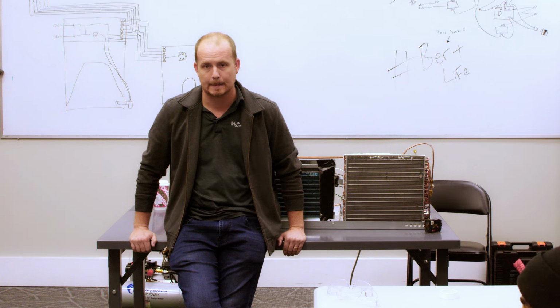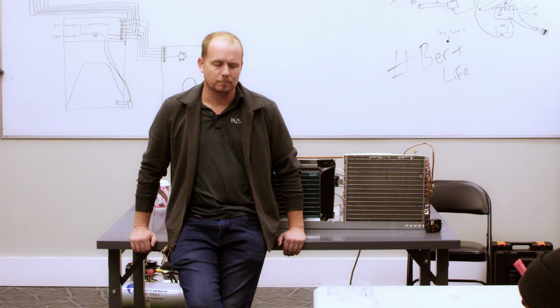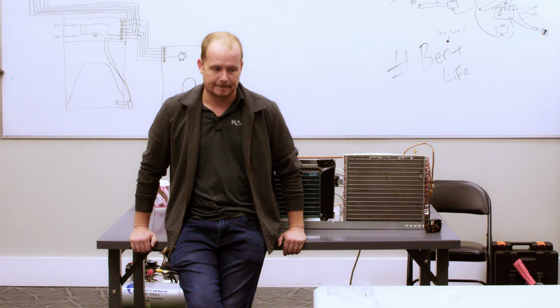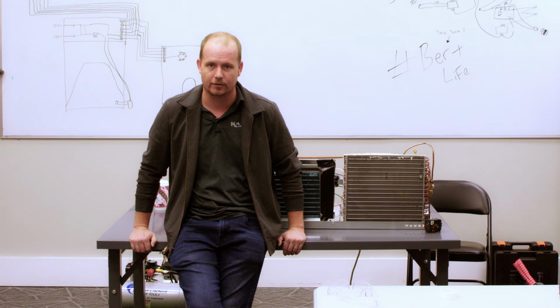So I think it's interesting to look at how it correlates with outdoor air temperature and indoor air temperature. If I'm not mistaken, and I could be because I have seen this, depending on the type of coil design, that number doesn't change a lot under the normal operating conditions. But if it's a microchannel, then it changes a lot more because microchannel has a much smaller internal volume.